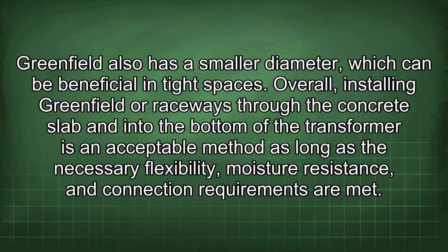Overall, installing greenfield or raceways through the concrete slab and into the bottom of the transformer is an acceptable method as long as the necessary flexibility, moisture resistance, and connection requirements are met.